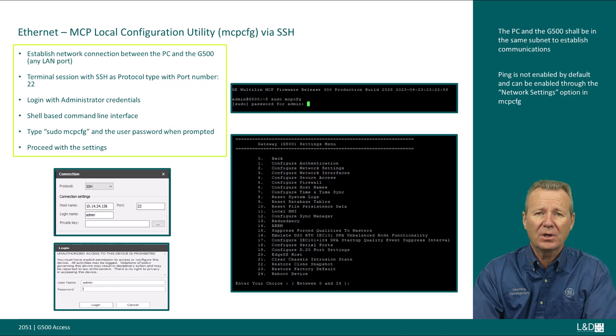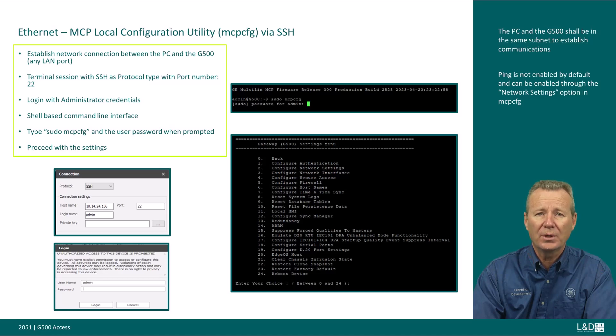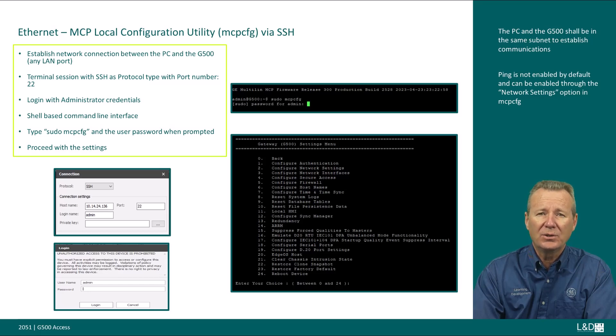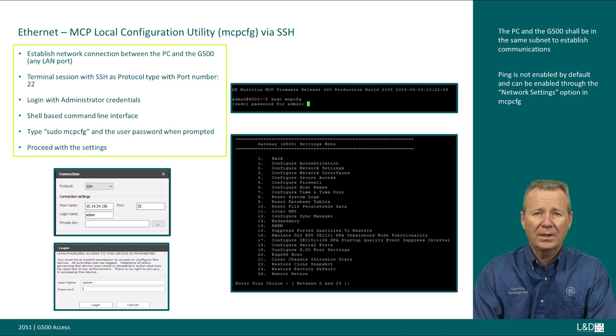The MCP Gateway local configuration utility can be launched remotely via SSH. The PC and the G500 shall be in the same subnet to establish a network connection. Launch a terminal application such as Secure Terminal Emulator from the DS Agile folder in the Start menu. Start a terminal session with SSH as the protocol type with port number 22. Log in using administrative credentials, then type sudo MCPCFG and enter the user password when prompted. A gateway settings menu will be shown and you can proceed with the settings.